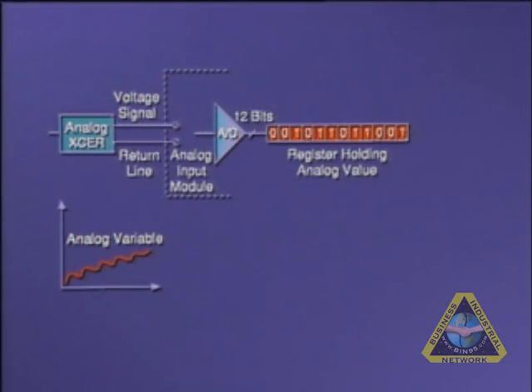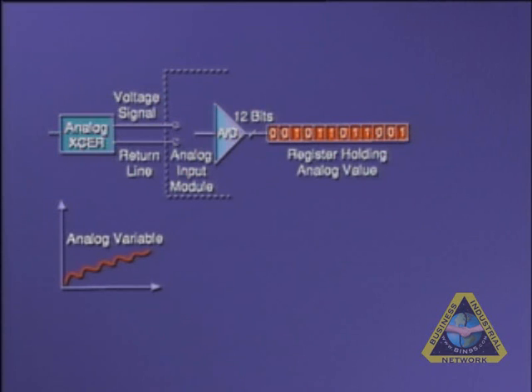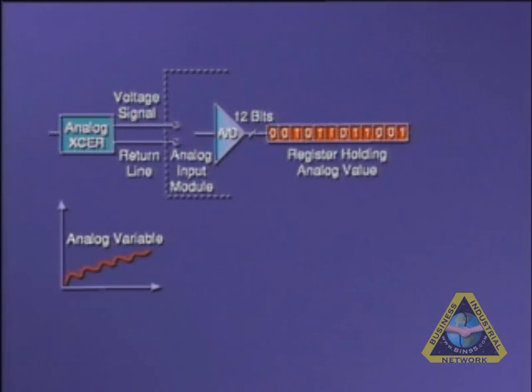During the control of the process, a signal variable is measured by a sensor and passed to the input module. The module itself transforms the signal into a discrete value according to the resolution of the A-to-D converter. In this example, 12 bits.